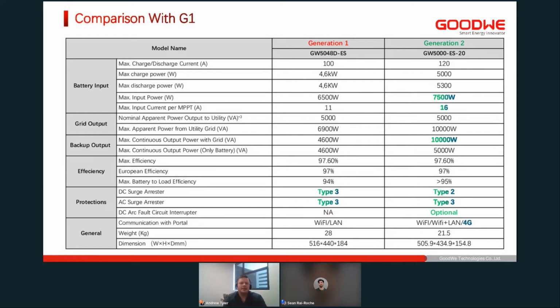And then for those markets, I know there are some markets in the EU or in Europe that require AFCI, or arc fault current interruption. This is something that can be purchased when the channel partner or whoever purchases the device. They can request that AFCI is installed as a feature, but we make it optional.